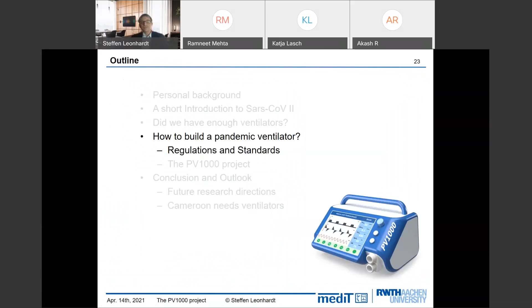Now, if you start such an enterprise like a pandemic ventilator, you have to follow regulation and standards. After all, the medical device industry is a regulated market, and there are standards like the European standard EN ISO 80601-2-12, which regulates conditions and requirements for ICU ventilators. With the substandards and attached standards, altogether there are about 600 requirements, quite a high number. Analyzed in detail, it boils down to a lot of monitoring requirements, especially oxygen, flow of gas, and pressure. It also requires alarming, for pressure supply, blockage, leakage, and so on, and safety methods, and redundancy with respect to a failed operation mode.